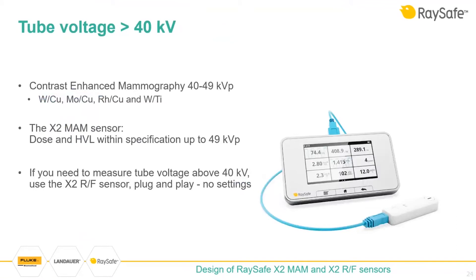One extra note about voltages above 40 kV: some machines have optional dual-energy or contrast-enhanced mammography functions. This involves two exposures — one with normal settings and a second with high kV above 40 kV and high filtration such as copper or titanium filter. This second exposure is either tungsten-copper, molybdenum-copper, rhodium-copper, or tungsten-titanium. For kVp measurements above 40 kV, use the X2 RF sensor instead of the MAM sensor — no settings required, just plug and play.